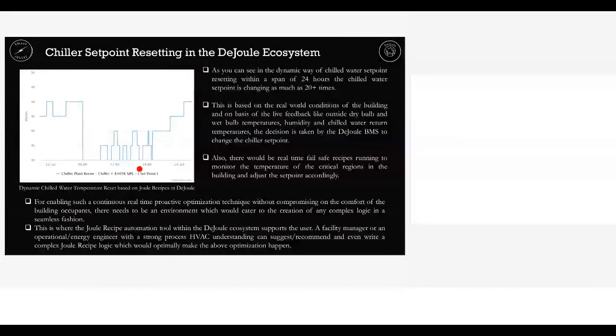No, it's 20 to 25 algorithms written by energy engineers who know the process - and I stress the word 'know the process' - how centralized air conditioning works. They analyze the data, find out the right combination right now, and deploy it through my BMS or IoT platform. That algorithm takes a real-time decision to change the set point at different times of day based on building conditions, occupancy, outside temperature, area comfort, whatever it is. For every 1 degree Fahrenheit change in the chiller set point, you save 3% of energy - that's 3% of chiller consumption.